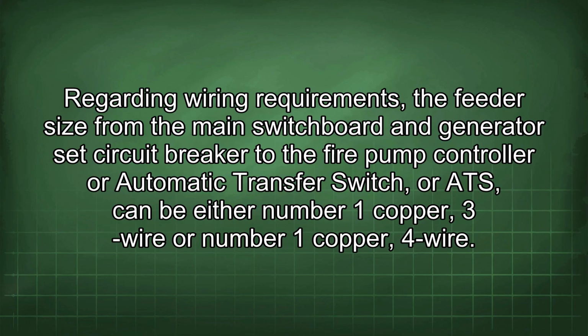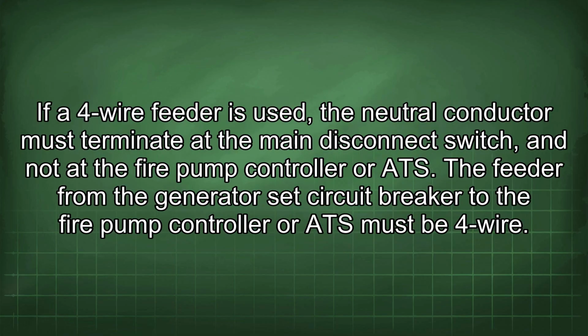Regarding wiring requirements, the feeder size from the main switchboard and generator set circuit breaker to the fire pump controller or automatic transfer switch, or ATS, can be either number 1 copper, 3-wire, or number 1 copper, 4-wire. If a 4-wire feeder is used, the neutral conductor must terminate at the main disconnect switch and not at the fire pump controller or ATS. The feeder from the generator set circuit breaker to the fire pump controller or ATS must be 4-wire.